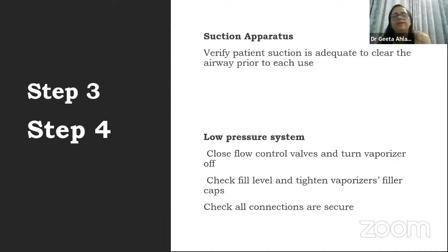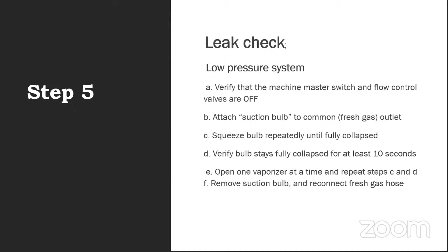In spite of checking all this, your suction apparatus should always be ready. Your low pressure systems, flow control valves, vaporizers: check all the connections whether they are in place or not. The leak checks, as you people are doing every day: with the master switch off, connect a suction bulb to it, squeeze it, press it. When the machine is off, there should be no gases coming out of it.